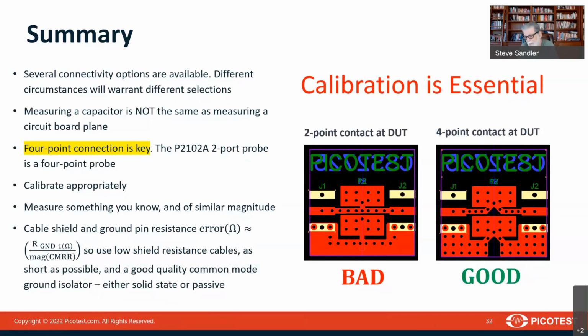So for example, in this measurement setup on the left, we connected the two connectors together first, and then we put these very short traces to the DUT. That's not a 4-wire measurement, it's only a 2-wire measurement, and it is going to add quite a bit of inductance. We really do need 4-point connection, so you can see how I did that on the right. We want to try to make sure that we do that with our 4-point probes and any 4-wire Kelvin measurements that we make. We want to try to make sure that we make this at 4 points.